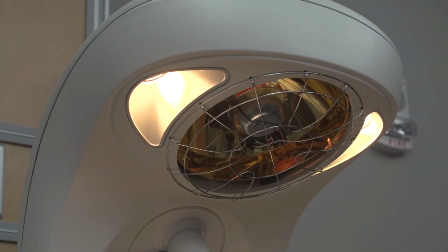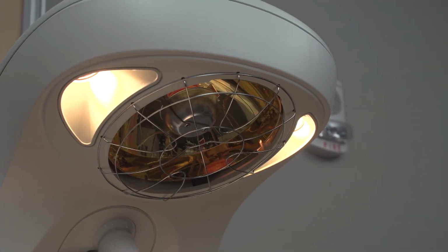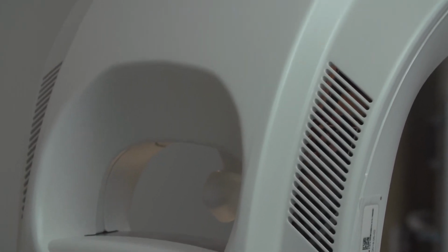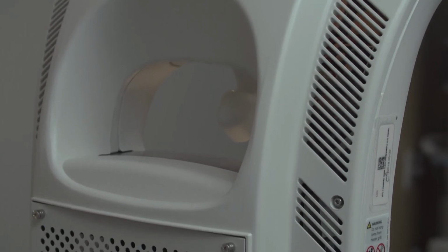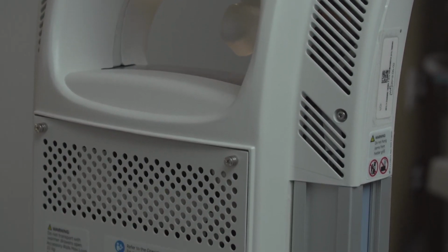Do not place tubing and hoses in the path of the radiant heater. Remember, do not touch the heater element, reflector, grill, or exhaust duct on the back of your warmer.